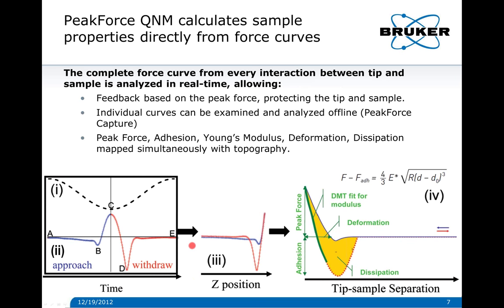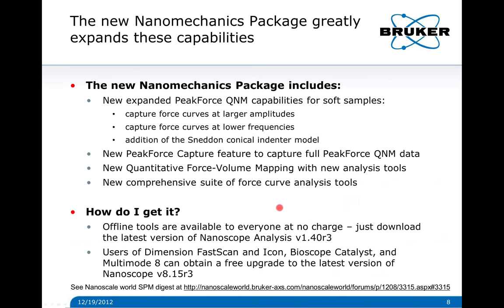Peak force QNM works by examining all the data collected during each cycle. Instead of just looking at the peak force for feedback, the QNM part has access to the whole force curve, so we can calculate different properties very easily. We can look at the peak force, the adhesion, the modulus by fitting the contact part of the curve, the deformation of the sample — which is the difference between the first contact and deformation at maximum force — and also the dissipation, which is often dominated by the work of adhesion.